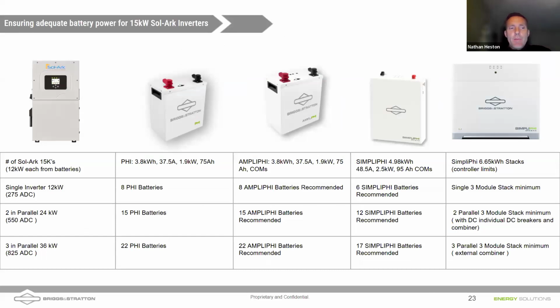It is important to keep in mind when you're designing a whole home system to make sure you have enough battery power to cover the full demand from the inverter. So for a Sol-Ark 15k, a single inverter can pull up to 12 kilowatts out of batteries, and you need to have a big enough battery bank that the battery bank's output can match the inverter's demand. So the number of recommended batteries is there on the screen.